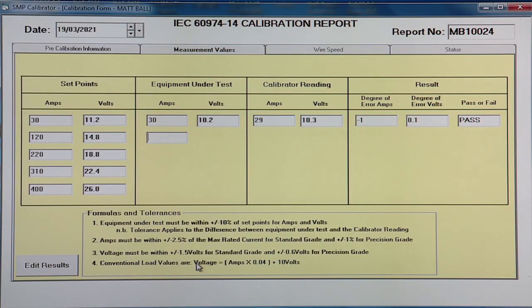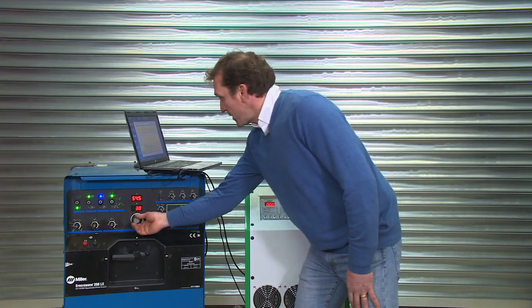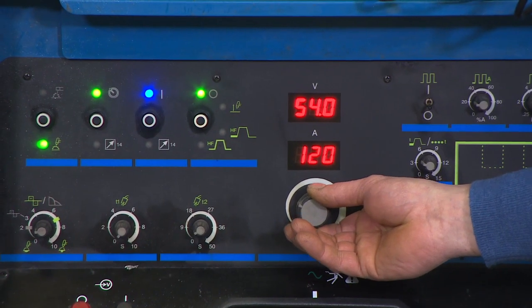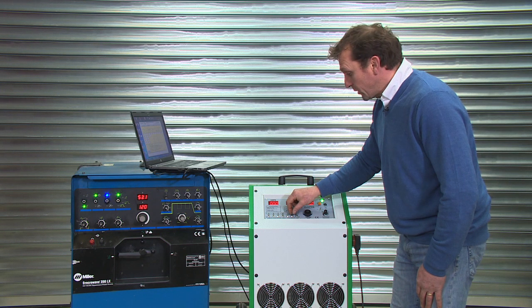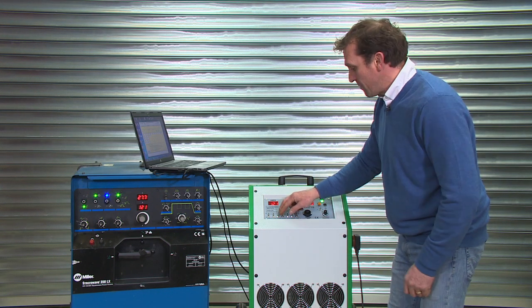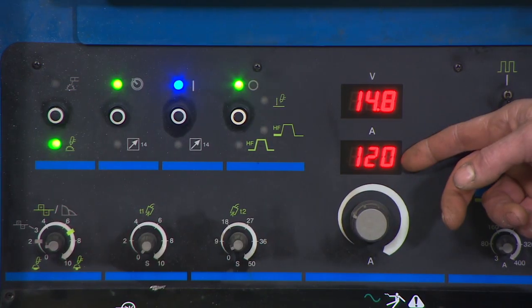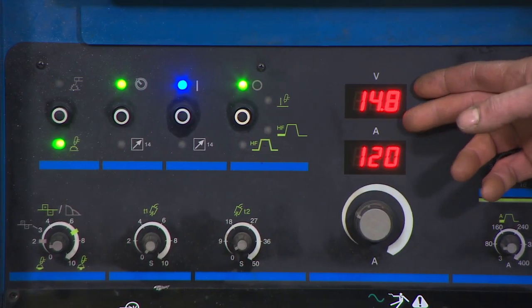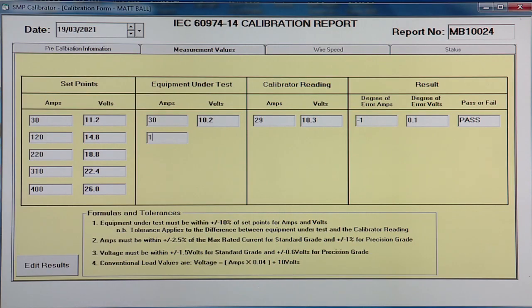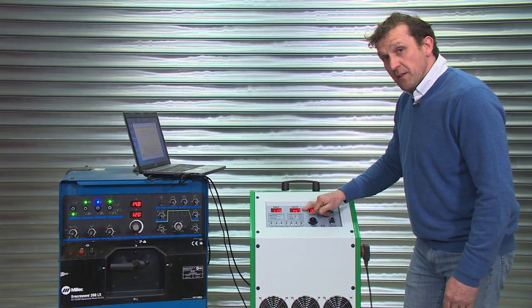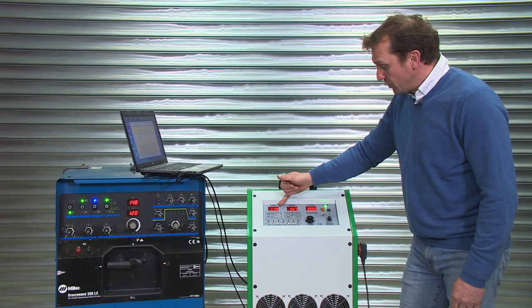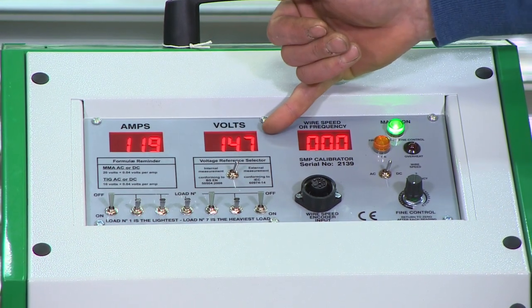Onto the second reading, 120 amps and 14.8 volts. So we set the machine to 120 amps and load up until we've got 14.8 volts within that 10% margin. We then enter the 120 amps and 14.8 volts into the program. And then the calibrator reading, 119 and 14.7.